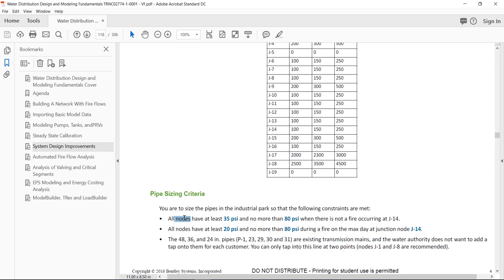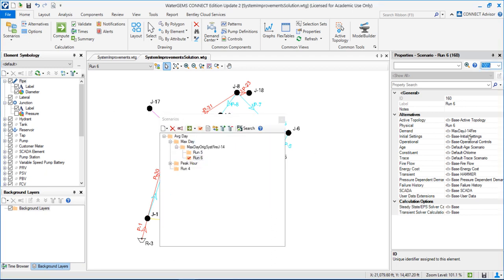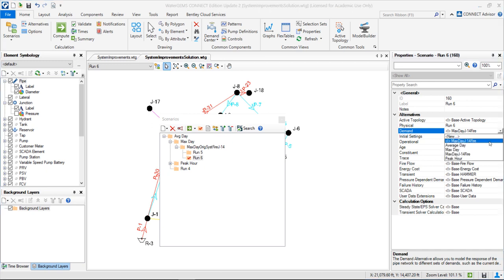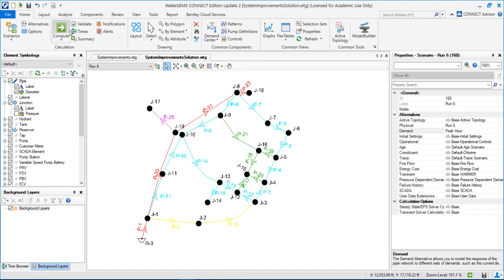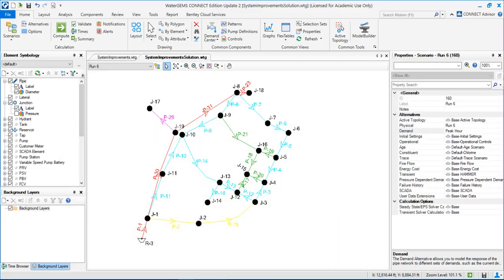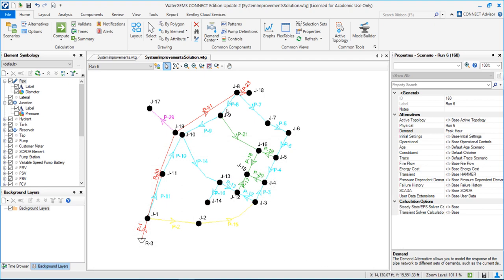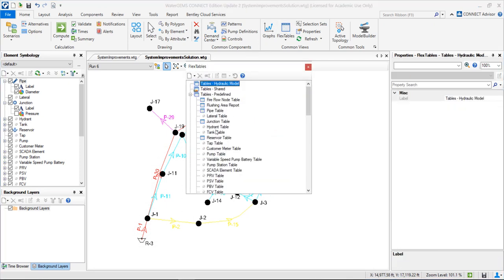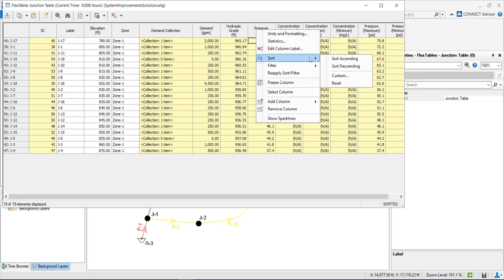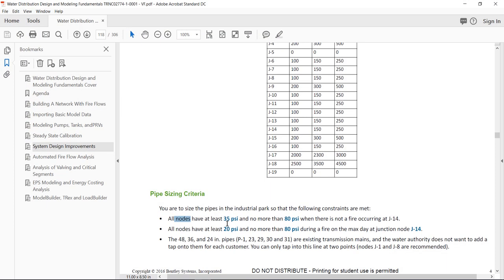In order to see if all nodes have more than 35 psi when there is not a fire, we should consider the peak hour, maximum hour demands. I can go to scenario number 6 and in the demand alternative input the peak hour alternative, then compute. To verify the pressure, I can open the flex table — the junction table — and sort all nodes by pressure ascending. My lowest pressure is 37 psi, which is higher than 35. So this criteria is achieved.